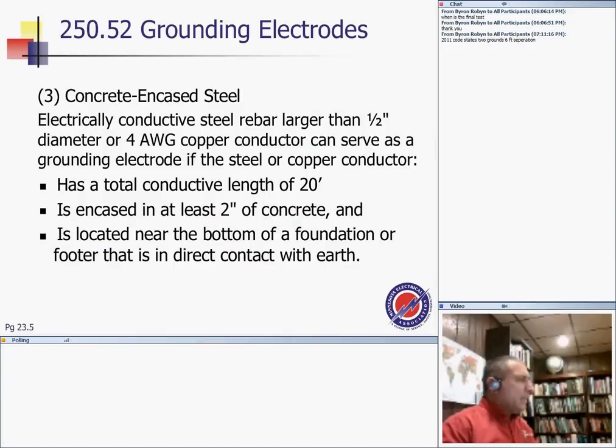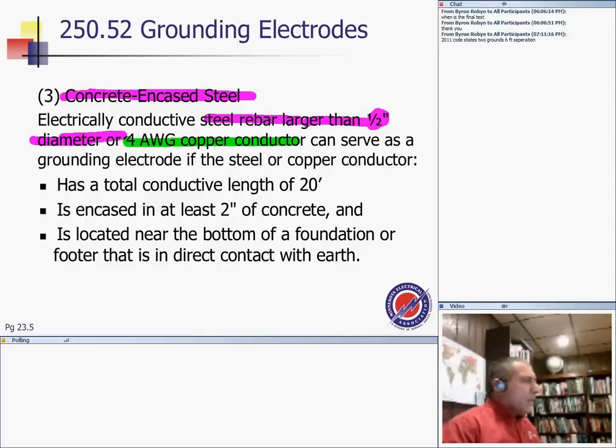In case that's the foundation of the building, guys, if you have a steel rebar larger than half an inch in there, and you can't maintain this, they allow you. They say, okay, no problem. Why don't you go stick a number 4 copper conductor in that foundation? Say the grounding. It could be your ground electrode system. The subsection, the length has to be 20 feet, and you have to encase it in 2 inches of concrete, and the foundation has to be in direct contact with Mother Earth.